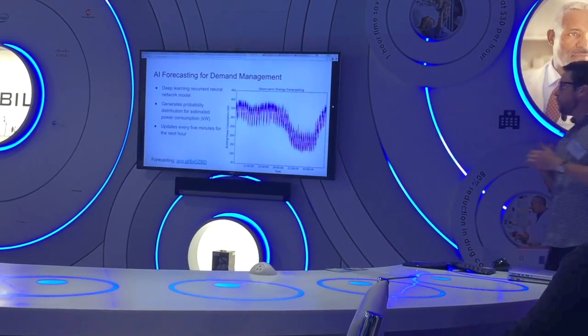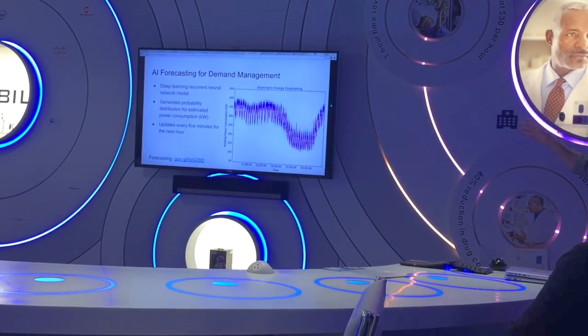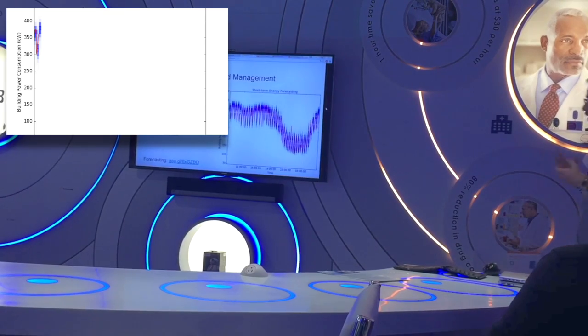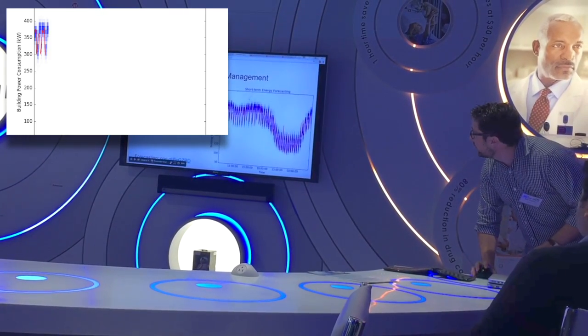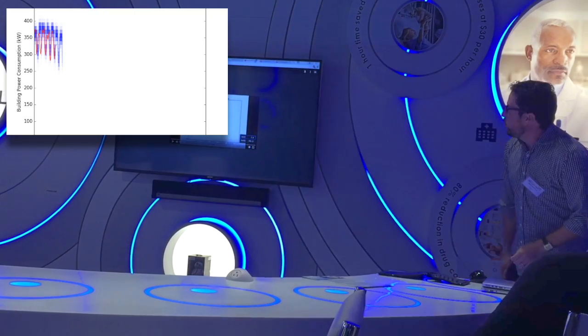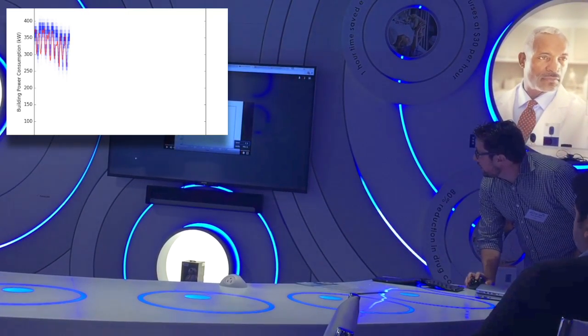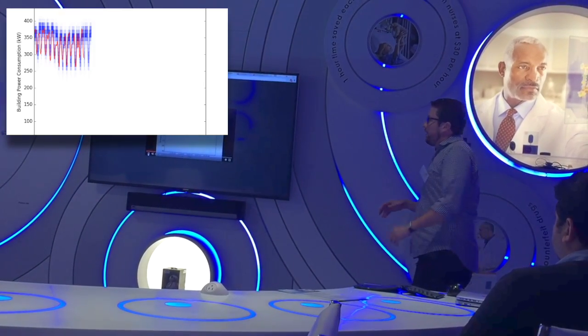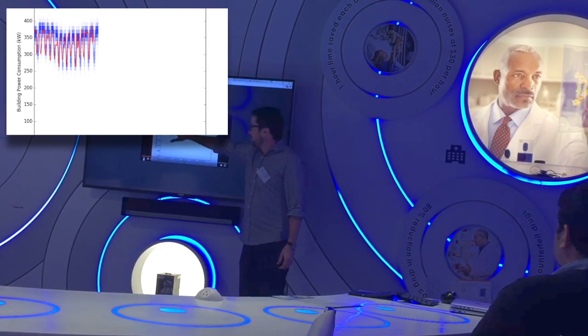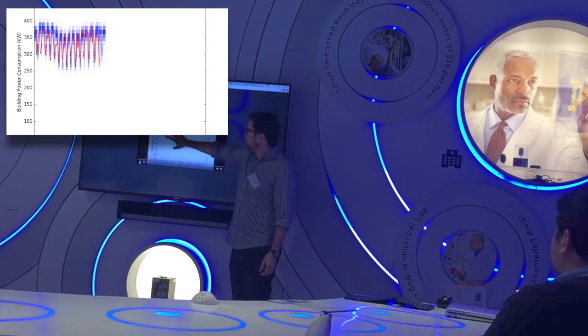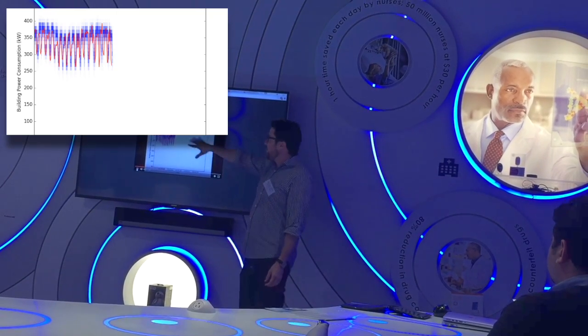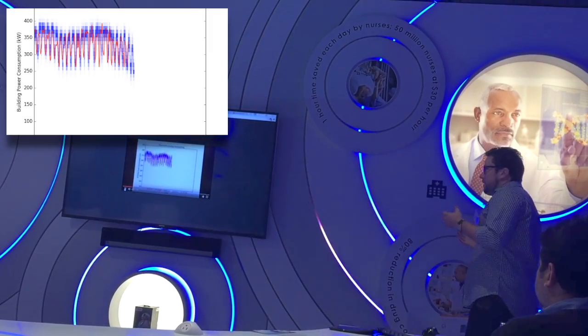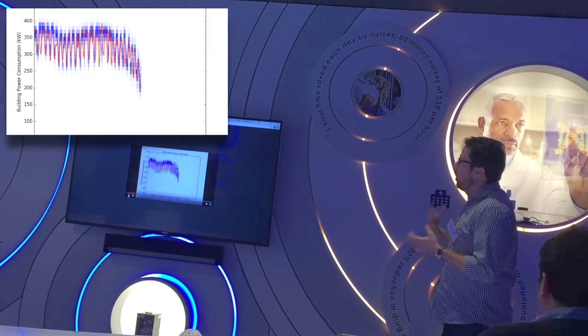So on the forecasting, for those that like machine learning terms, we use a deep learning recurrent neural network model. Essentially what that does is it generates a probability distribution for estimated power consumption and I have a little animation of kind of how that works. What we're doing here is every five minutes we're looking out one hour and we're sort of drawing these blue dots, kind of the probability distribution where we think energy is going to land, and then the red line that's following it is the actual demand. So you can see it's a pretty accurate model, and essentially what we then do is as I mentioned, we compare that to a known threshold.